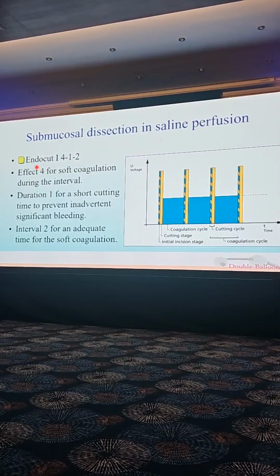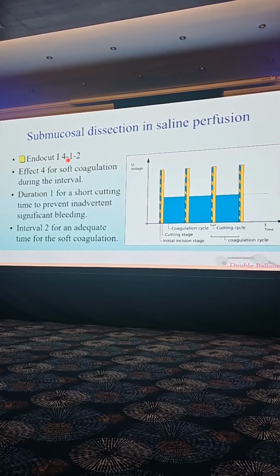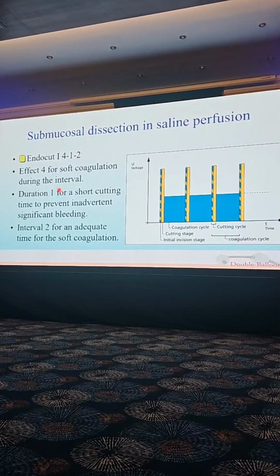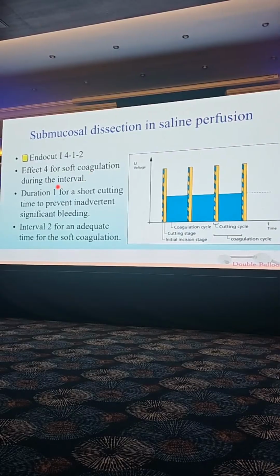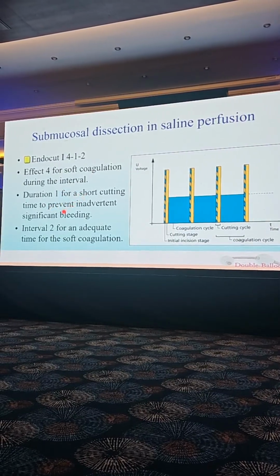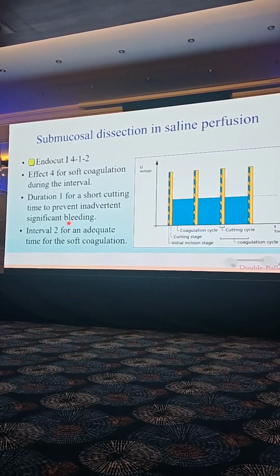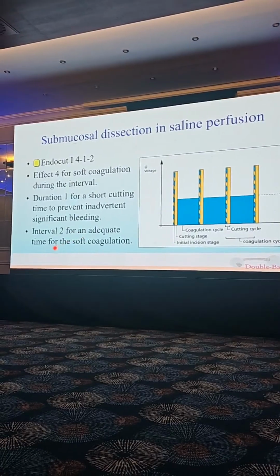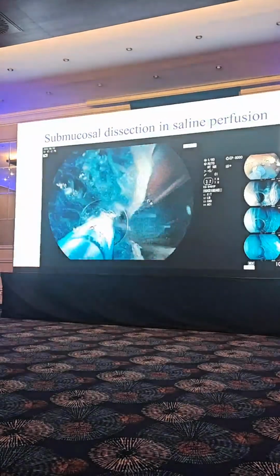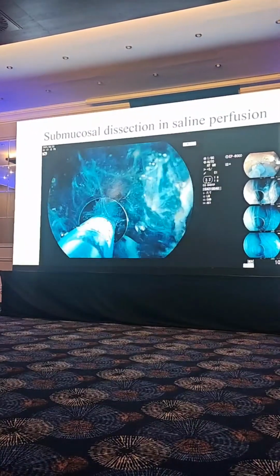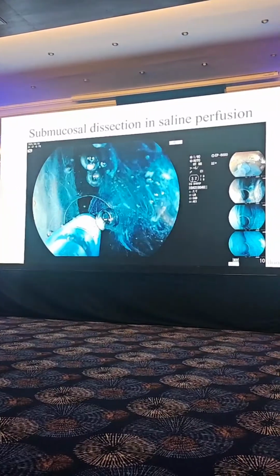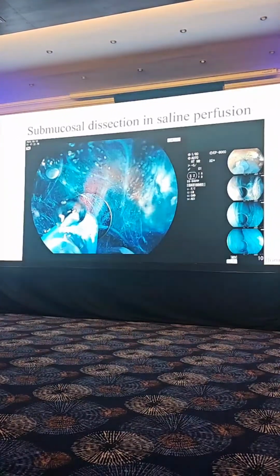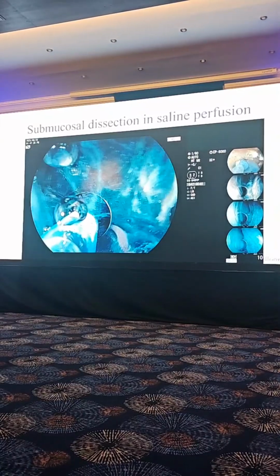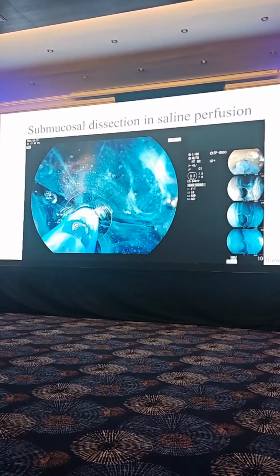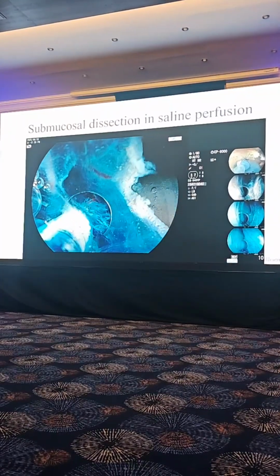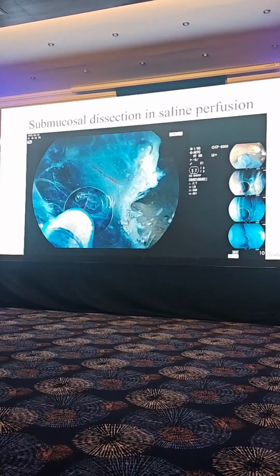So now I use the Endocut I, effect 4, duration 1 and interval 2 for the submucosal dissection. So the effect 4 is for soft coagulation during the interval, duration 1 for short cutting time to prevent inadvertent significant bleeding, and interval 2 for an adequate time for the soft coagulation. So this is what I do in the ESD saline immersion method. Using the Endocut I, effect 4, duration 1, interval 2, if there is a blood vessel, then I change to soft coagulation and coagulate, and cut. After the coagulation, I cut with the Endocut.